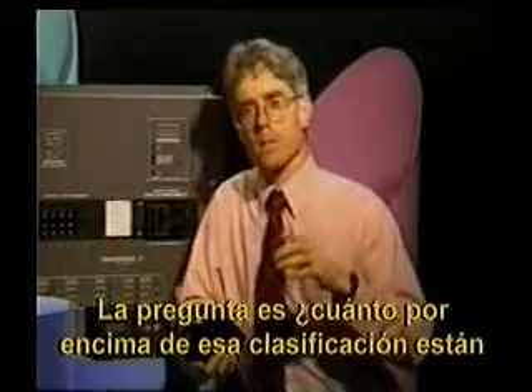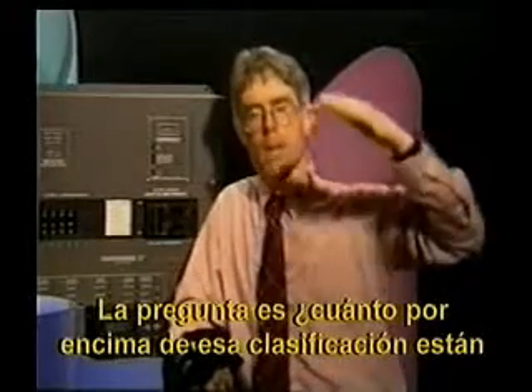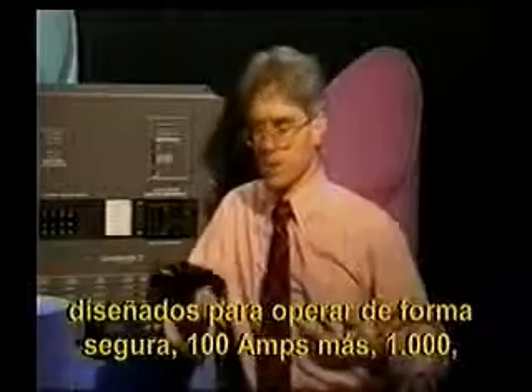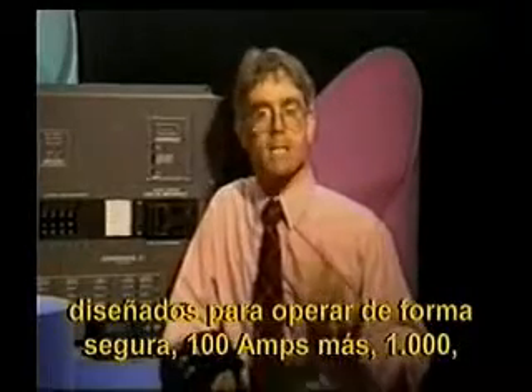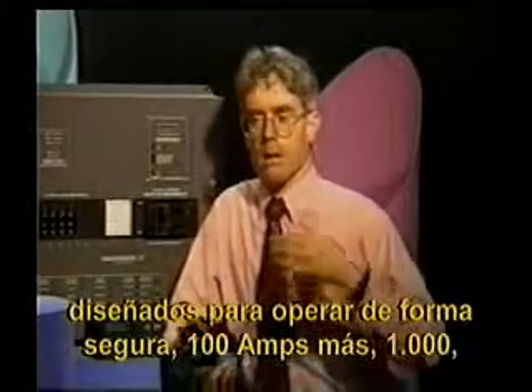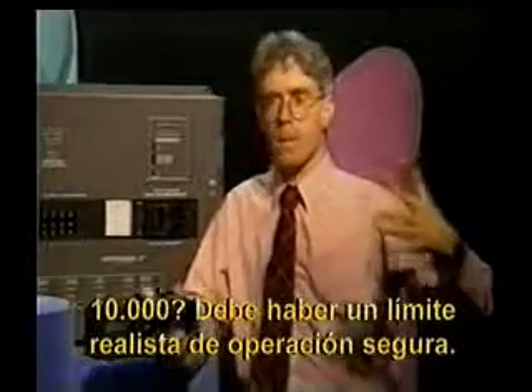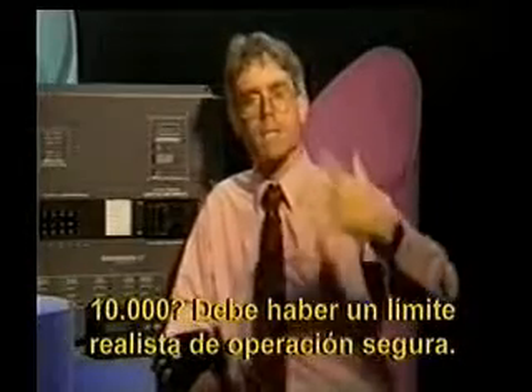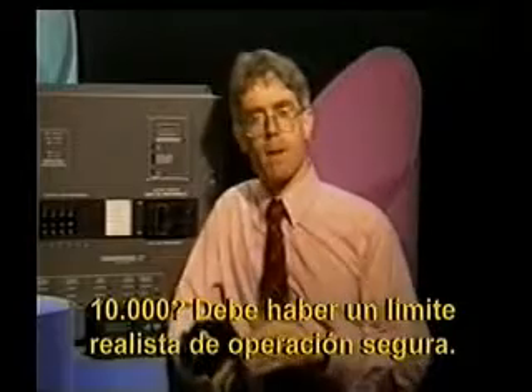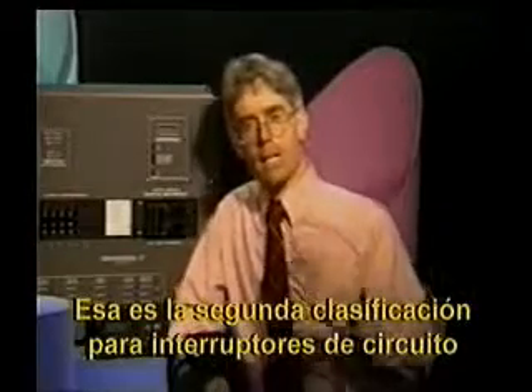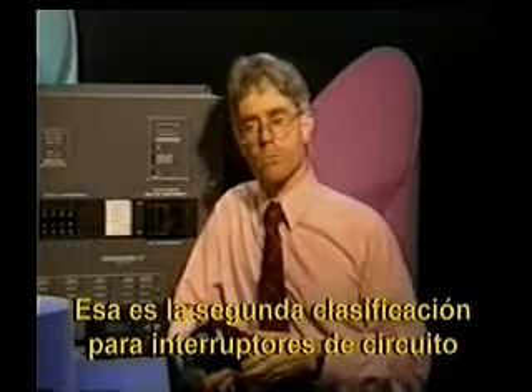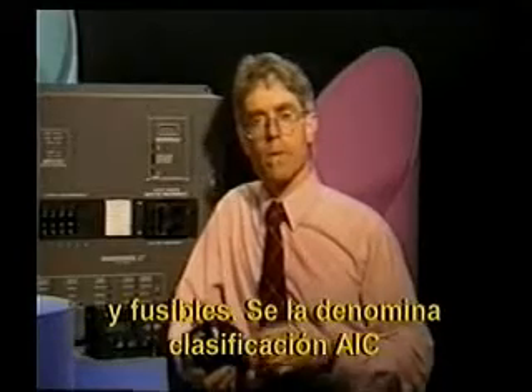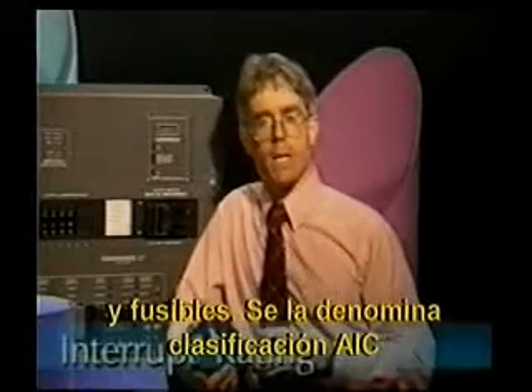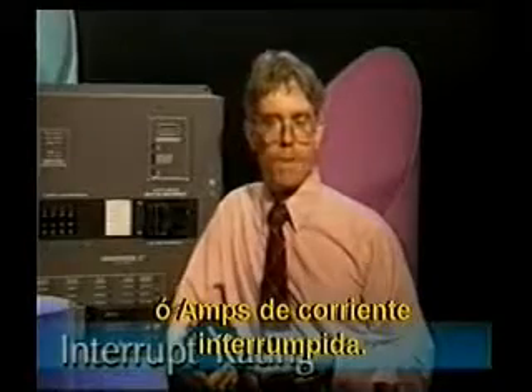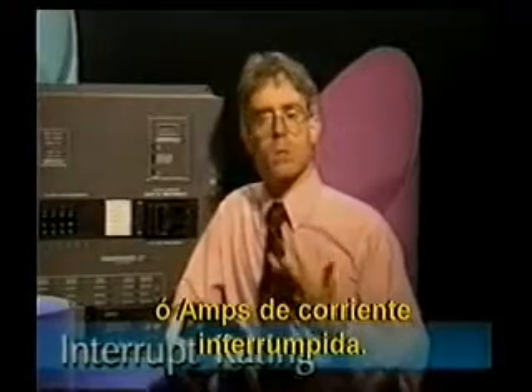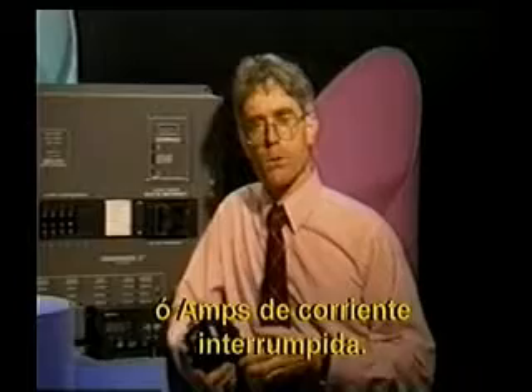The question is, how much above that rating is the circuit breaker or the fuse designed to operate safely? 100 amps more, 1,000 amps, 10,000, a million amps? There's some realistic upper limit to its safe operation. That's the second rating for circuit breakers and fuses. It's often referred to as the AIC rating, or amps of interrupt current rating, or interrupt rating for a circuit breaker or a fuse.